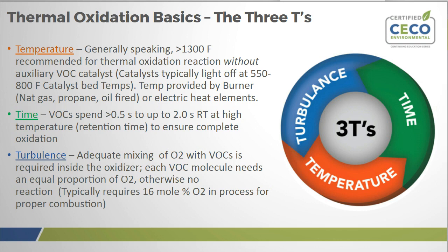The time element: VOCs can spend typically a half second up to 2 seconds or more of retention time or residence time at these higher temperatures to ensure complete oxidation. You basically bake the VOCs at a certain temperature. And you also do need turbulence in the combustion chambers while you're doing the temperature. And the turbulence comes from adequate mixing for the oxygen. You want to have oxygen with the VOCs.